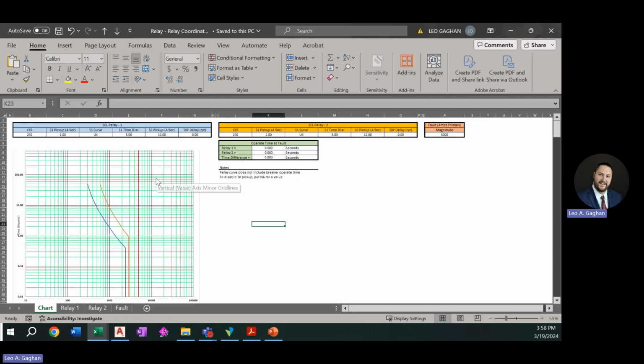So what you can do here on this blue portion is model a relay. What you can do here on the orange portion is model a relay. And then this here is intended to be the fault magnitude. The colors line up, right? Blue lines up with blue curve, orange lines up with orange curve, and red lines up with the red fault. This gives you the operate time in seconds for relay 1, relay 2, the time difference.